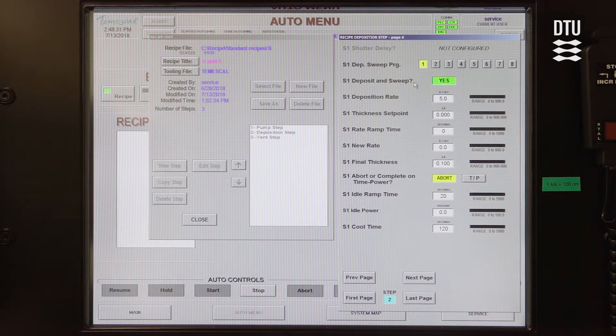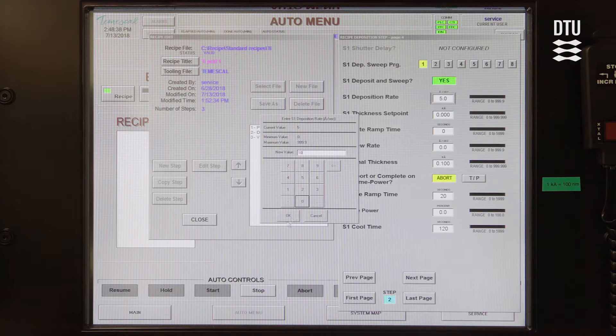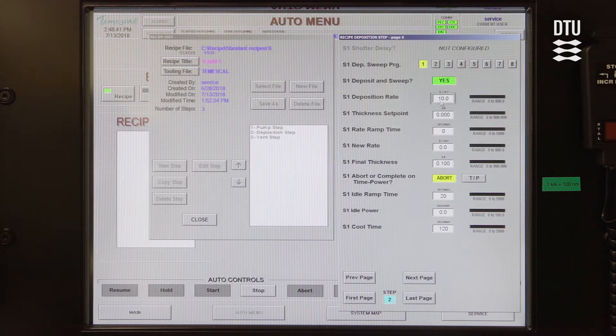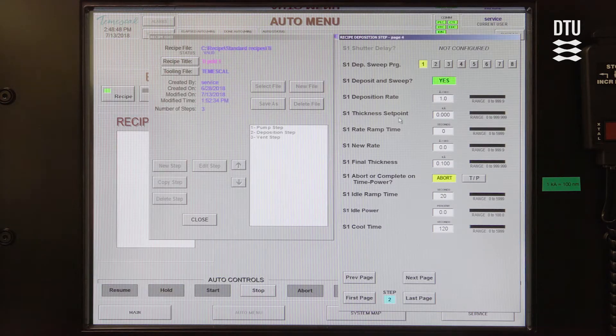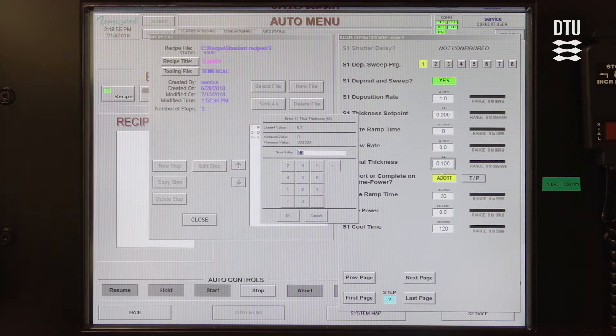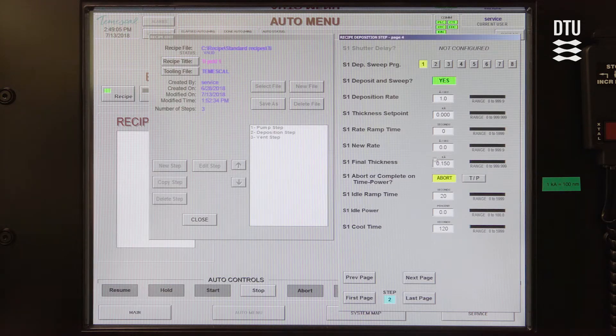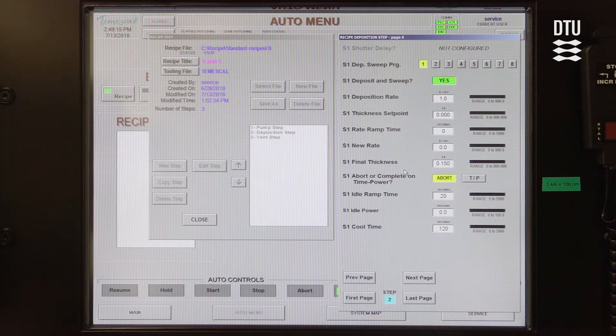Go to next page — page 4. Here you can set the deposition rate. Perhaps you want to deposit at 10 angstroms per second, or maybe that's a bit fast for titanium if you're making a thin layer and you choose only 1 angstrom per second. Apart from the deposition rate, you can also choose your final thickness. Let's say we want 15 nanometers instead of 10 — I press 0.15 because the units here are in kilo angstroms, so you need to convert from nanometers.